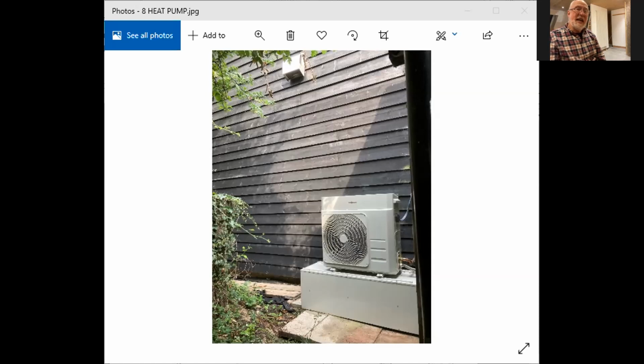A person sitting down like me, sitting in this room, is generating 100 watts. Cooking and showering should generate another few hundred watts. So, I mean, we're well within the 3 kilowatts or 3.5 kilowatts we need for hot water and heating, with a 6 kilowatt heat pump, plus the casual gains from lighting, people, cooking, etc.